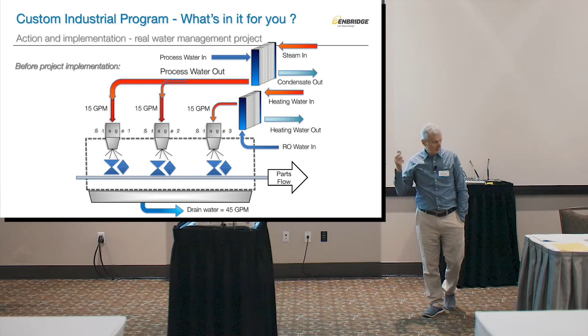$276,000 investment, condensing economizer, all the piping, all the metering, all the testing that we've done, saves them 657,000 cubic meters of natural gas a year. 657,000. Savings $183,000. Our incentive, that's the one that we worked for 4 years. We gave them this incentive level 4 years prior to this project implementation, because they tried and tried and tried and couldn't get funding from the corporate office. And we kept trying and trying and trying.